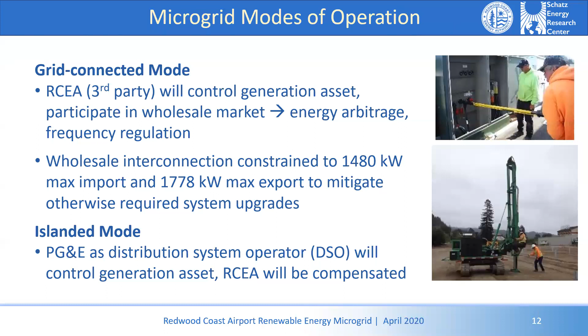The one other point that I jumped over, the wholesale interconnection: Matthew described what the capacities were of the wholesale system, basically 2.2 megawatts of PV, 2.2 megawatts and 8.8 megawatt hours of battery storage. We are constraining the export to 1,778 kilowatts and the maximum import for charging of the battery to 1,480 kilowatts. And we've just chosen to do that to mitigate system upgrades that otherwise would have been necessary to support the full capacity and would have added cost to the project that was not sustainable in terms of the way the project is being financed and funded. So that's just a particular detail. On to the next slide, please.